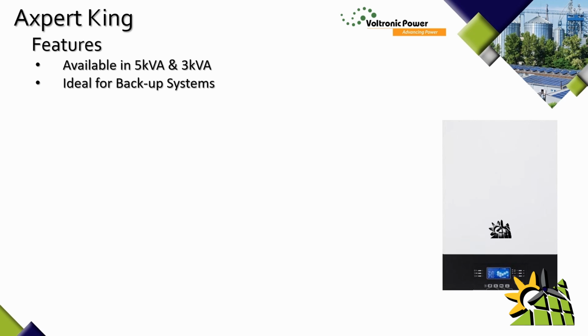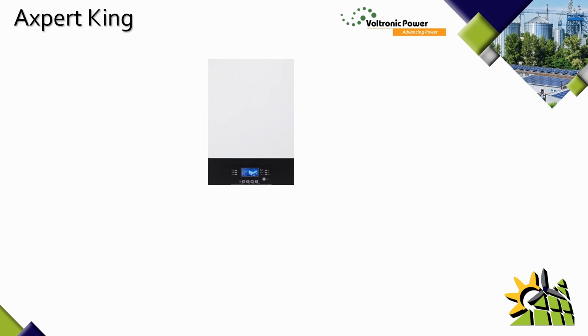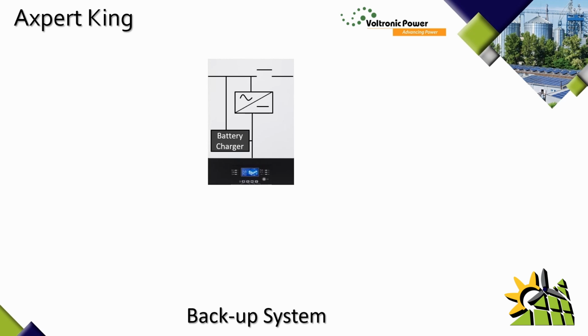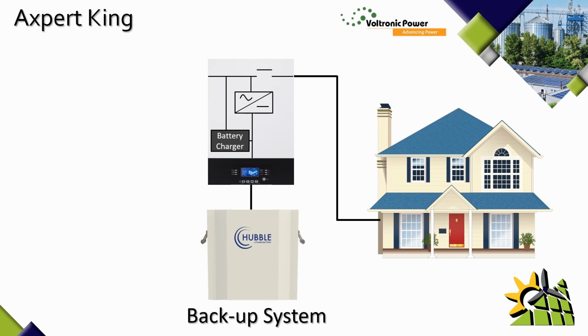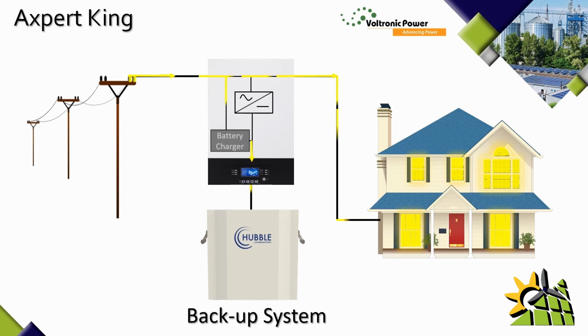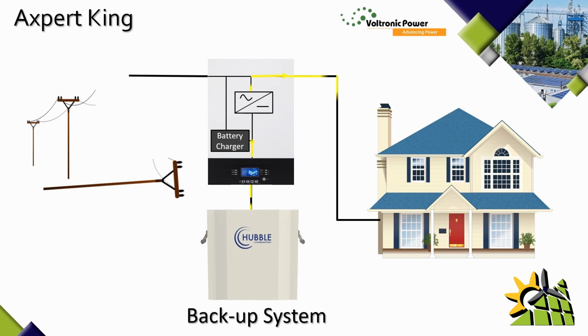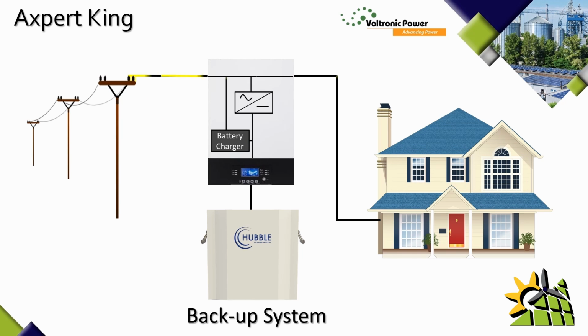This inverter is ideal for backup systems. Now, what makes it ideal for a backup system is the fact that it's got a built-in battery charger. So on a backup system, you would connect a battery to the inverter. It will also be connected then to the load. You would also have an AC input line that gets connected to the grid. Now, under normal circumstances, the grid will run through the inverter to the load, as well as charging the battery. Once the battery is fully charged, the inverter will continuously provide power to the load. If the grid becomes unavailable due to a power outage, the inverter will automatically switch over to battery mode and supply power from the battery to the load. When the grid is restored, the inverter will automatically switch back to grid mode and start charging the battery again.